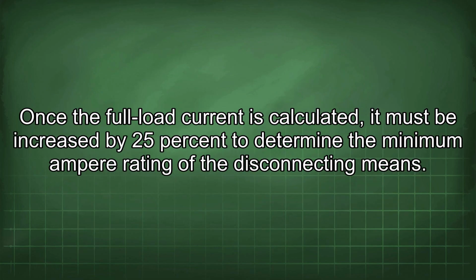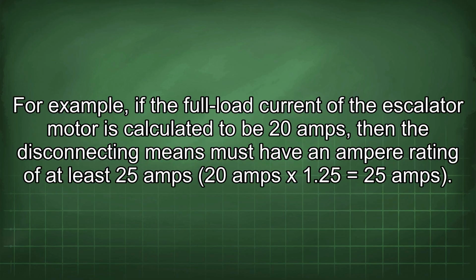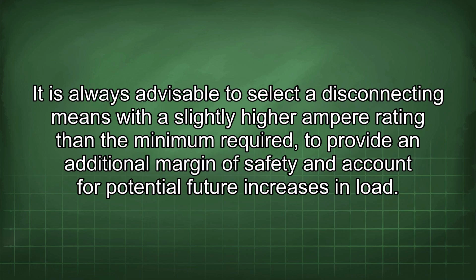Once the full load current is calculated, it must be increased by 25% to determine the minimum ampere rating of the disconnecting means. For example, if the full load current of the escalator motor is calculated to be 20 amps, then the disconnecting means must have an ampere rating of at least 25 amps. 20 amps x 1.25 equals 25 amps. It is always advisable to select a disconnecting means with a slightly higher ampere rating than the minimum required to provide an additional margin of safety and account for potential future increases in load.